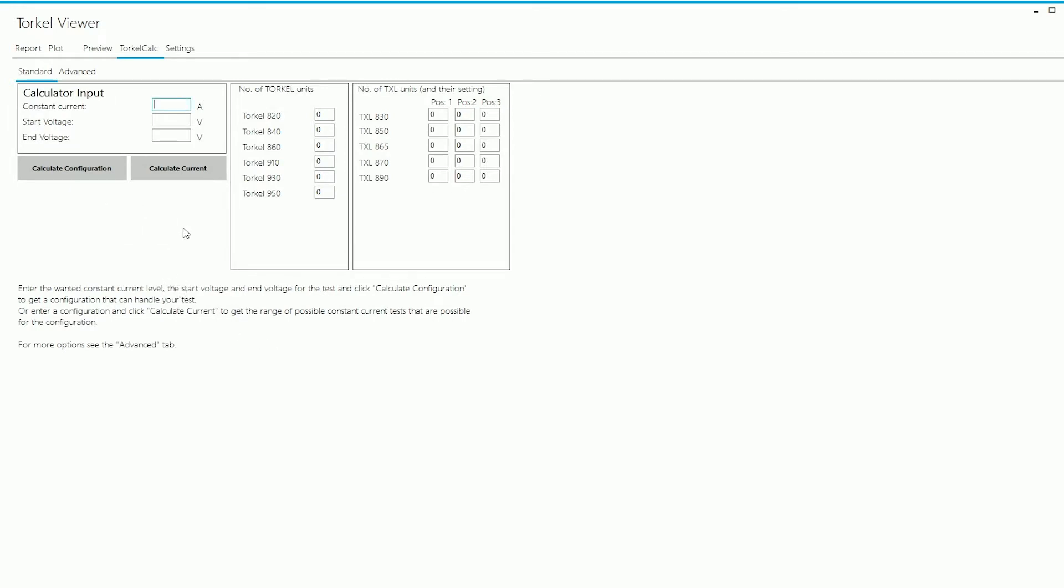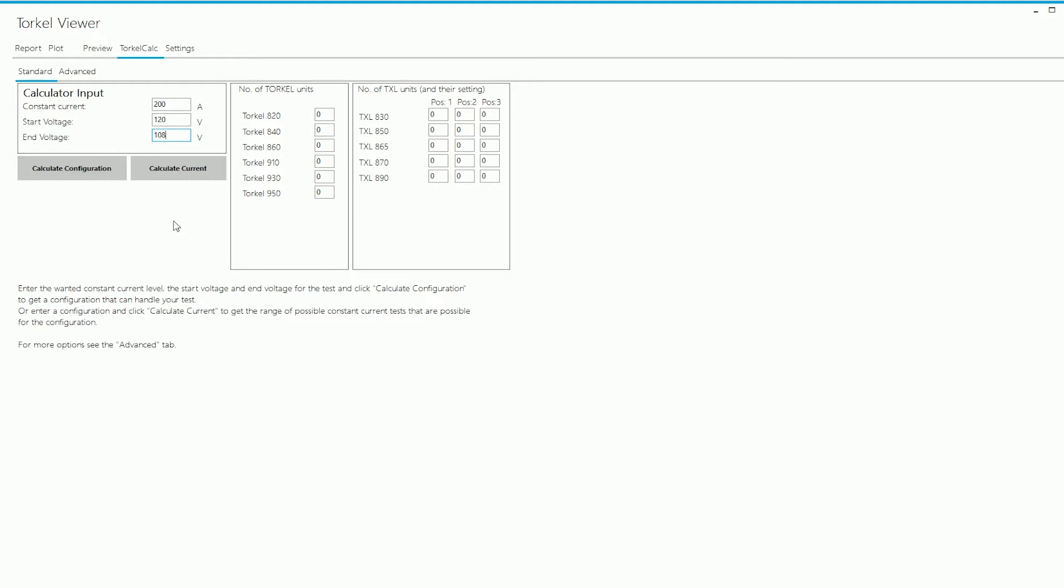To determine the configuration needed to run a particular test, I would need to enter the test parameters, namely the test current, the start voltage and the end voltage. So let's say I'm planning to run a constant current test at 200 amps on a 120 volt battery string and let's say the end voltage is supposed to be 108 volts for that test.